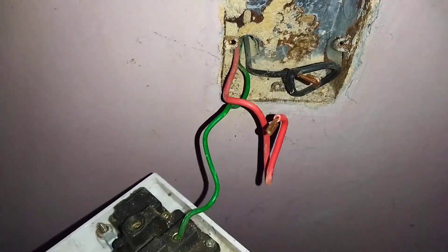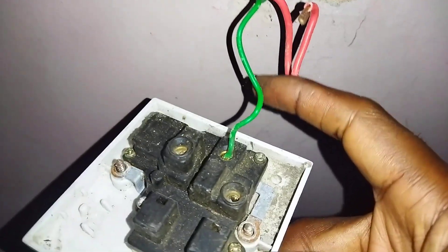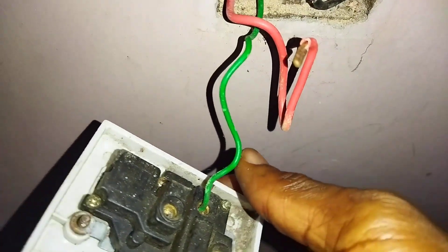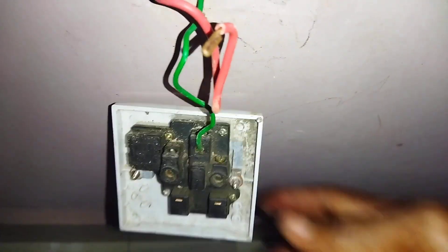This is a circuit point of a building. This is a live cable, this is a neutral, and we have a third wire here. If you look at the terminal where it's fitted, we have this earth sign — the earth is being supplied with a green cable. I'll be going to the distribution board right now to show what is happening there.